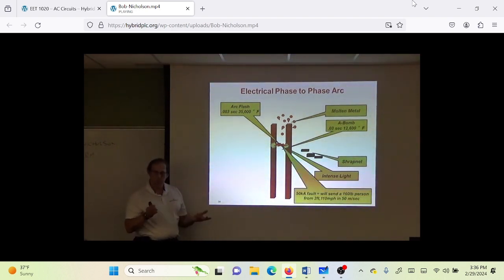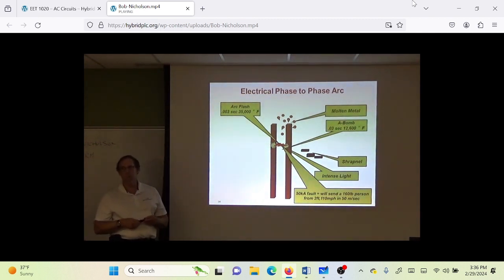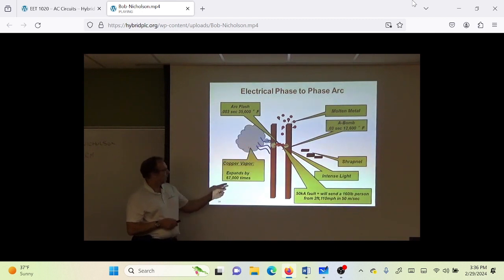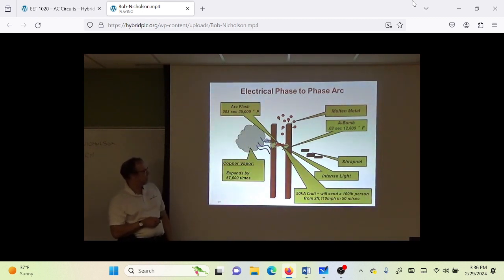The pressure, you saw pressure. A large arc flash can take a 160-pound person and accelerate them by pressure from 0 to 110 miles an hour in 51 thousandths of 1 second. That's getting hit really hard, really fast. Copper will expand 67,000 times its volume, and that turns into vapor, and it goes in your lungs.